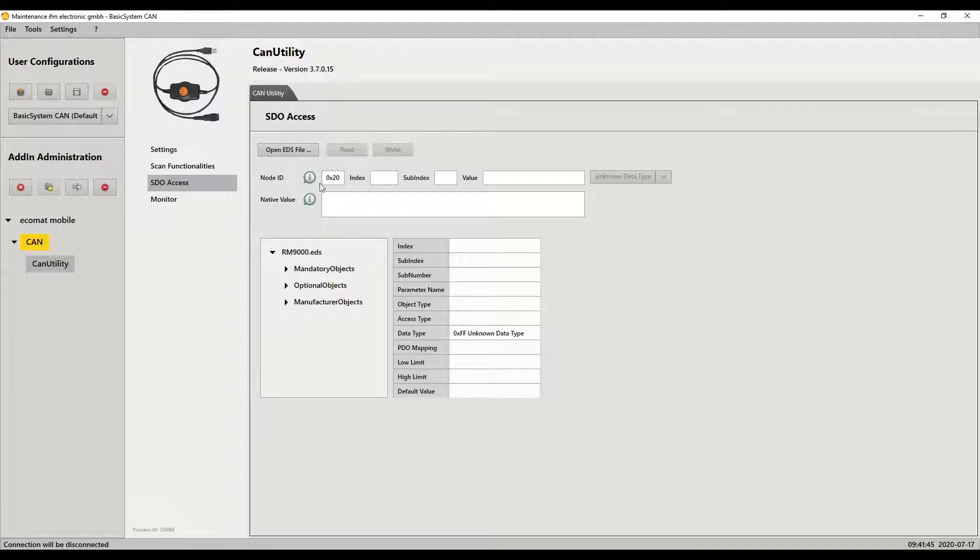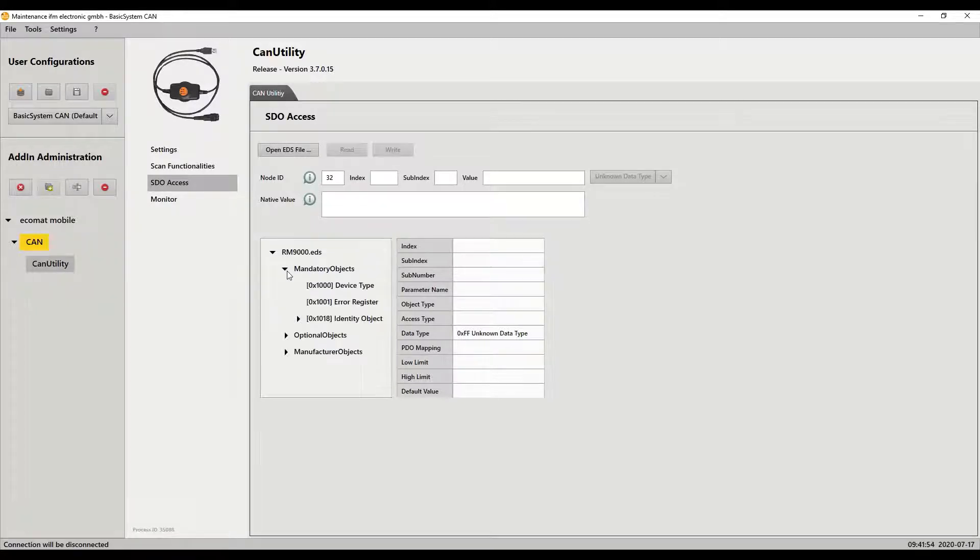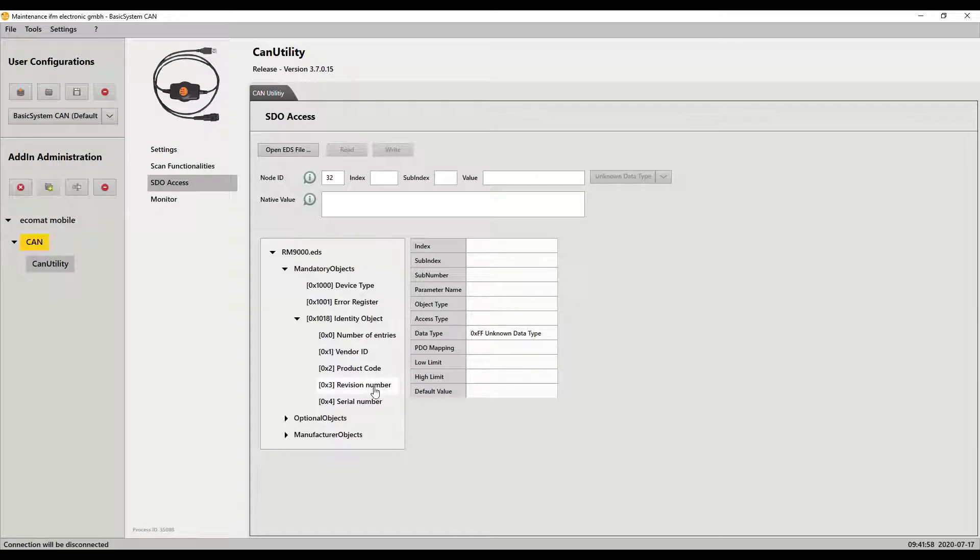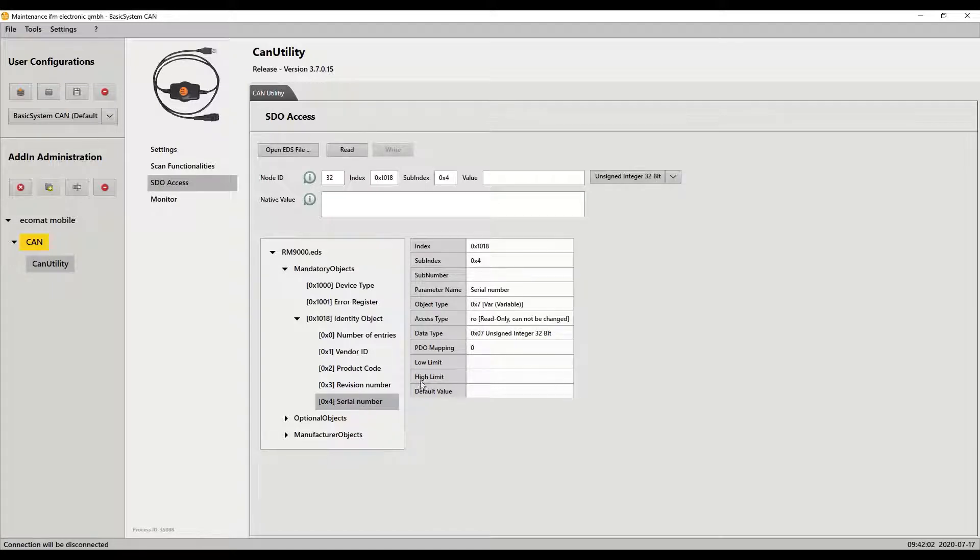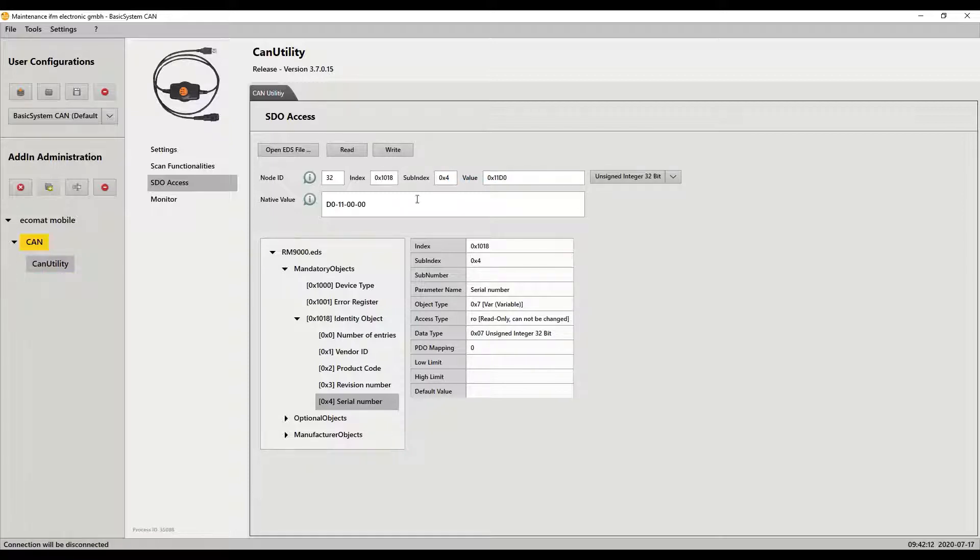So the first thing I want to do is change the node ID to 32. You see it defaults to 0x - that means it's a hex value - but if you don't put the 0x you can just put the decimal value. So I've got the node ID of 32. I'm going to go down here and select the serial number which will automatically then fill in the index and the sub index of exactly where I need it, which is really handy, and I just click read. It sends the command out and the data comes back and there is the serial number for this particular device.